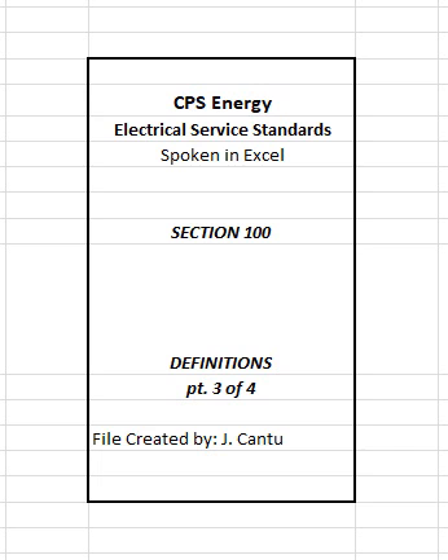H. Primary voltage cable to high-rise residential buildings. When CPS Energy-owned primary voltage cable serves transformer vaults with transformers supplying secondary voltage service to grouped or individual meters, the point of delivery will be in the transformer vault or room at the secondary spades of the transformer. All CPS Energy-owned conductors shall be effectively outside the building. Refer to definition of conductors considered outside of building.